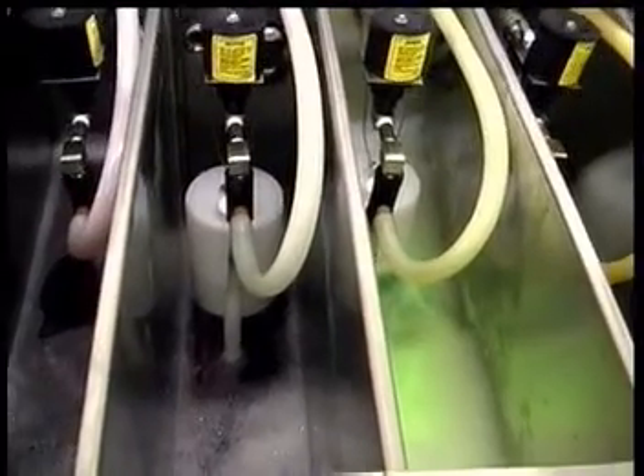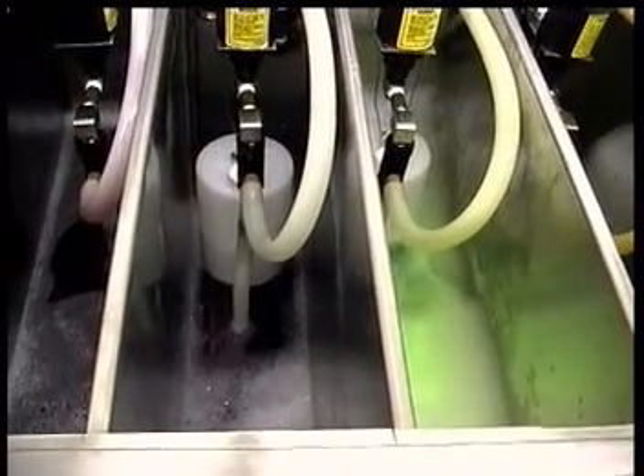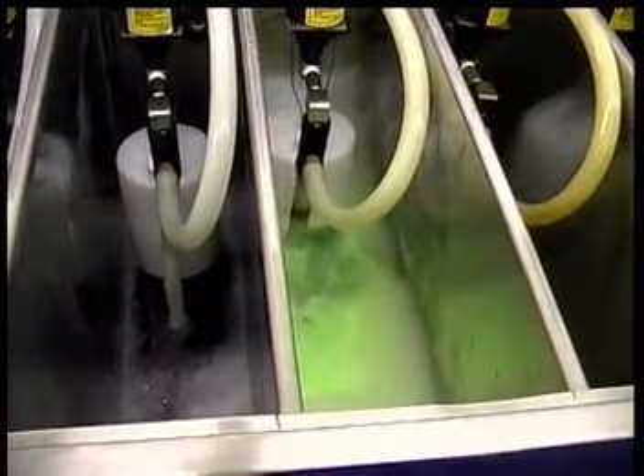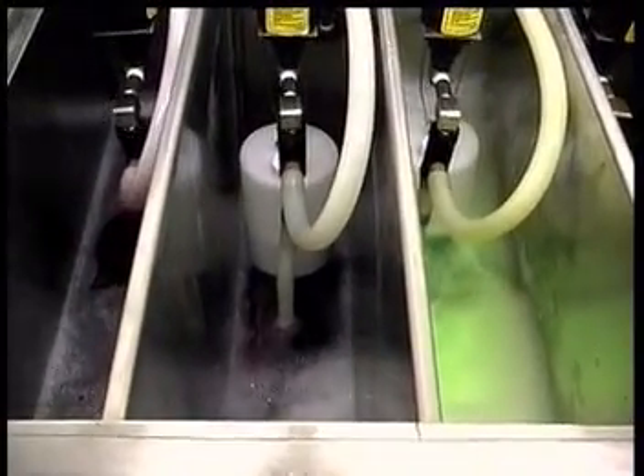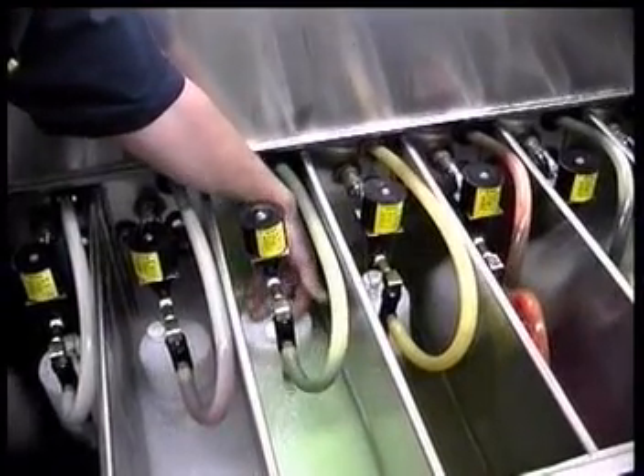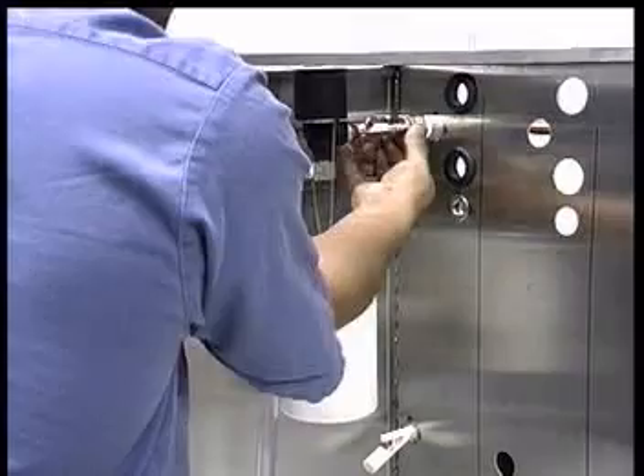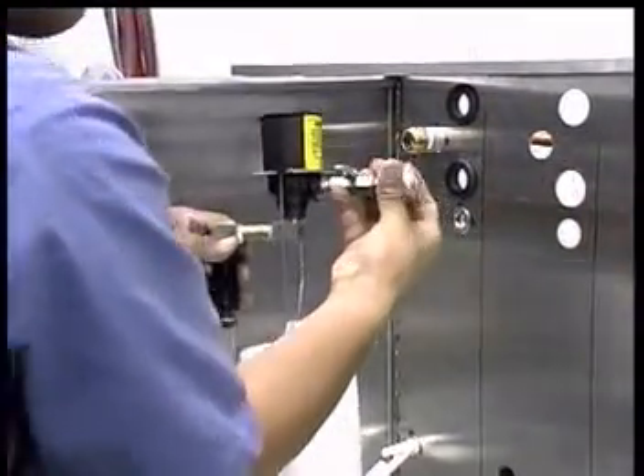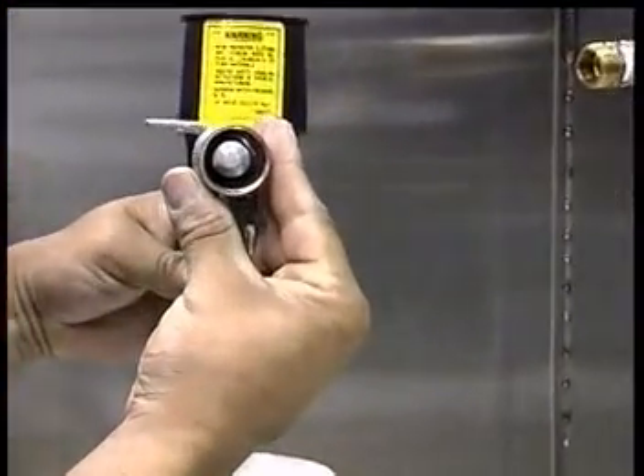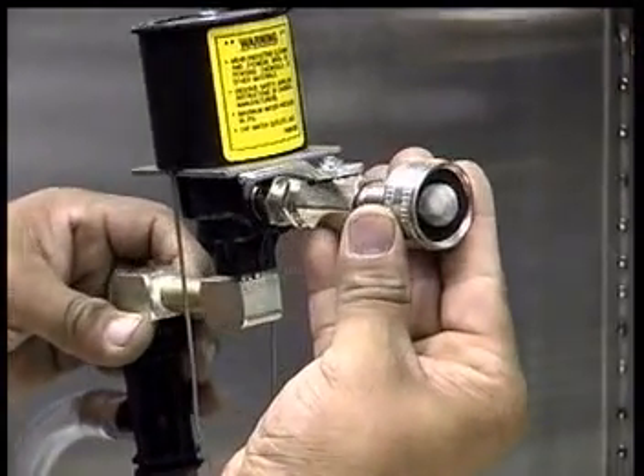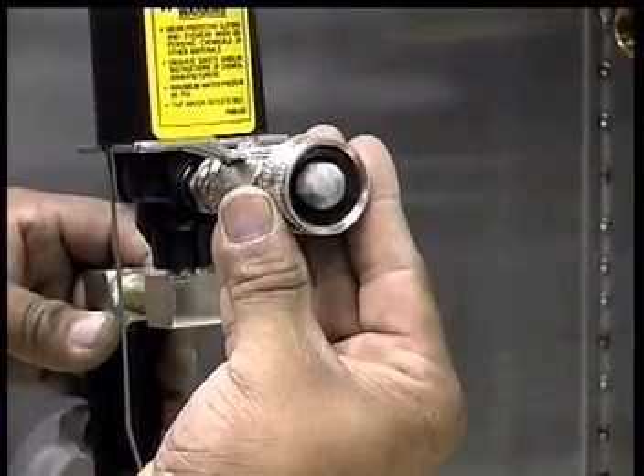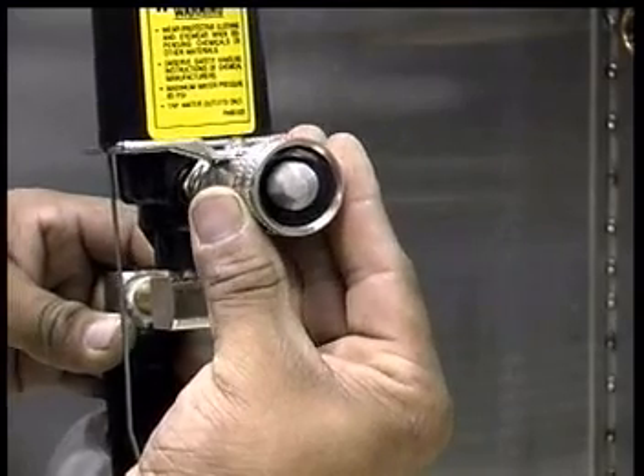If the tank is empty, check for liquid in other tanks and that city water is available. If water is present in other chemical tanks, check for a stuck float and that the quarter-turn valve is open. If all is okay, turn off the water and check the screen filter on the Hydraminder inlet. If the screen is clean, follow the service steps under the Hydraminder chapter for valve repair.